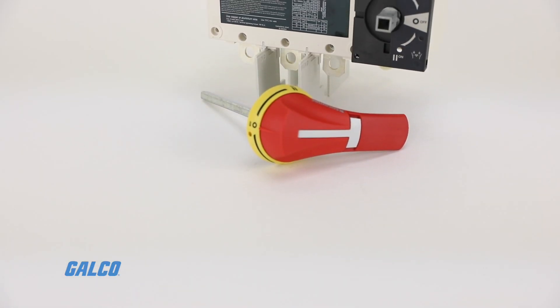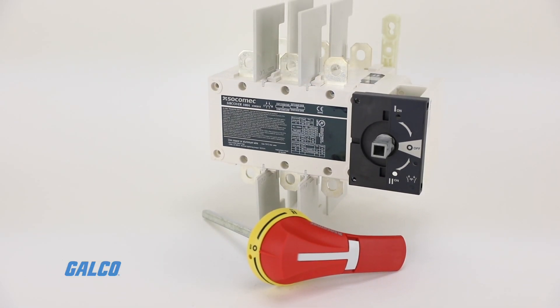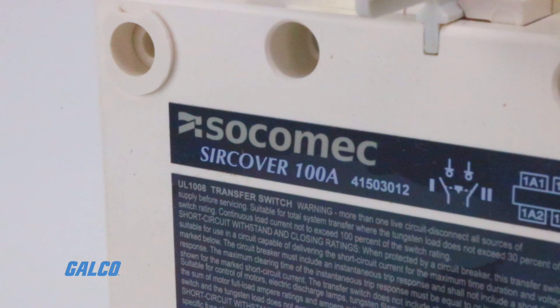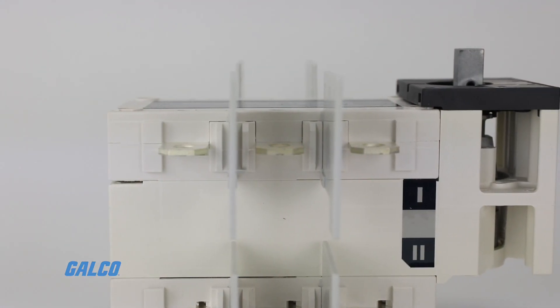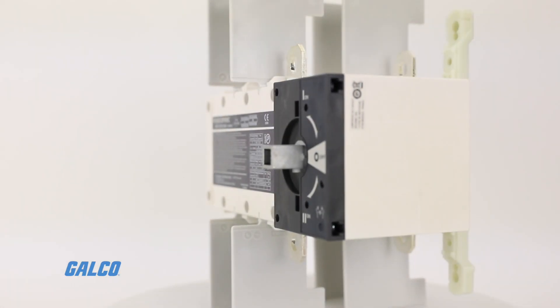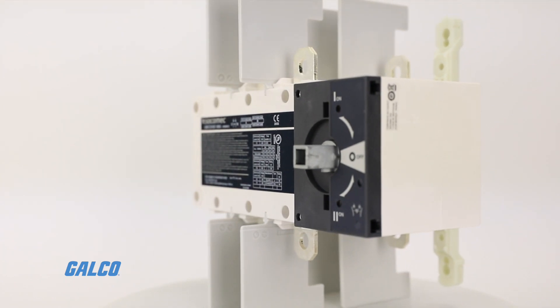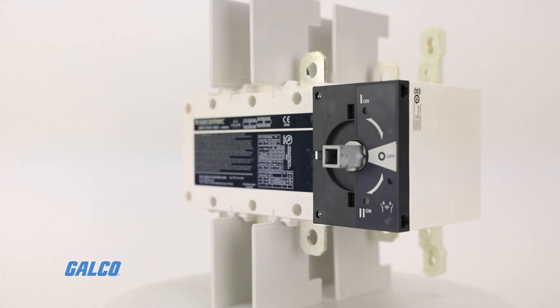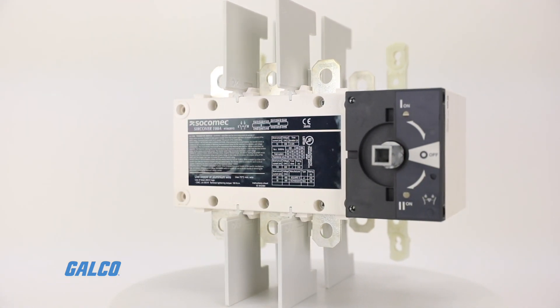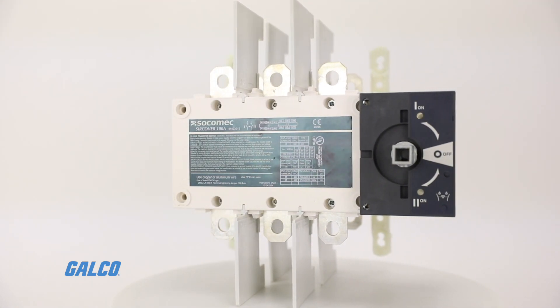The Socomec SIRCOVER is a family of manually operated transfer equipment designed to provide on-load transfer between two sources for any low voltage power circuit in compliance with UL1008 requirements for optional standby systems as described in NEC article 702.